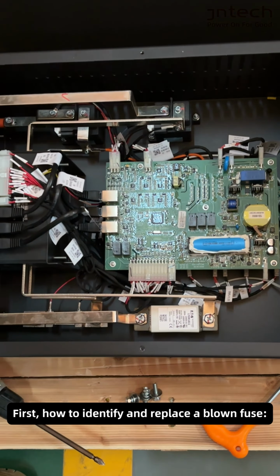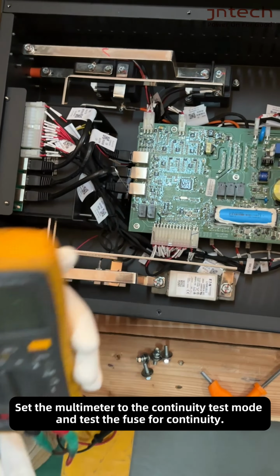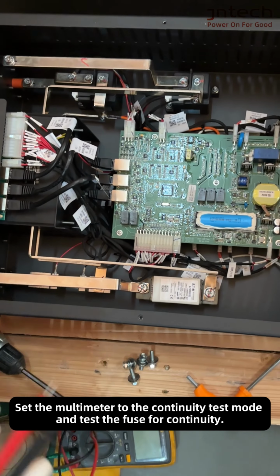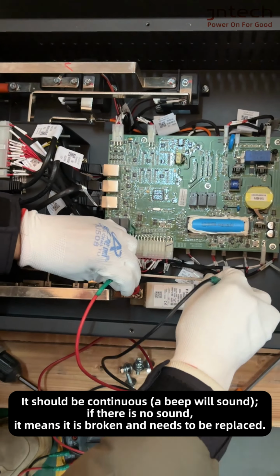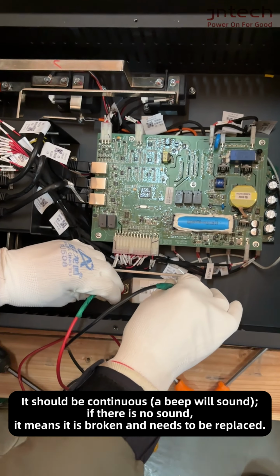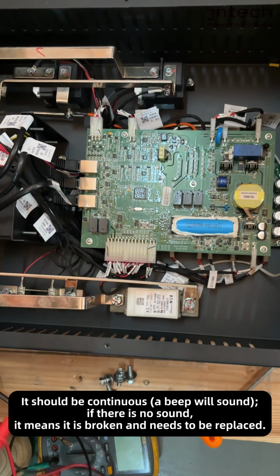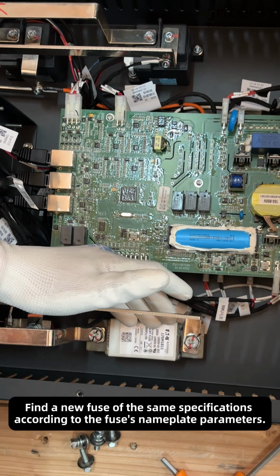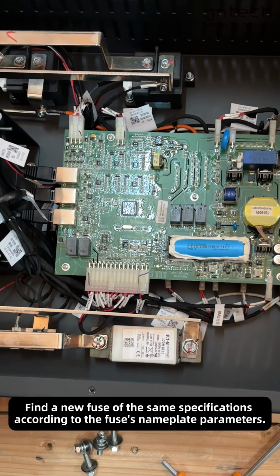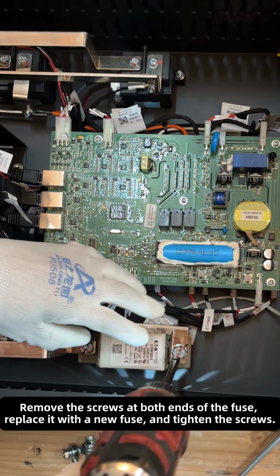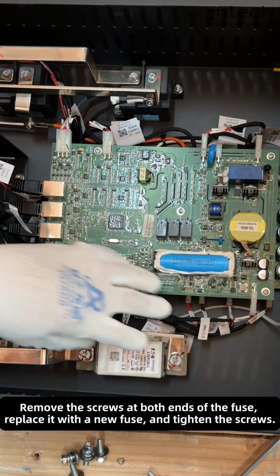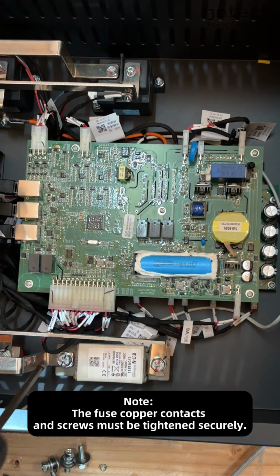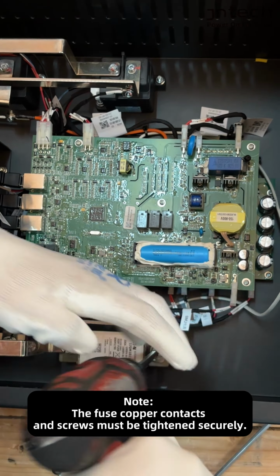First, how to identify and replace a blown fuse. Set the multimeter to the continuity test mode and test the fuse for continuity. It should be continuous. A beep will sound. If there is no sound, it means it is broken and needs to be replaced. Find a new fuse of the same specifications according to the fuse's nameplate parameters. Remove the screws at both ends of the fuse, replace it with a new fuse, and tighten the screws. Note, the fuse copper contacts and screws must be tightened securely.